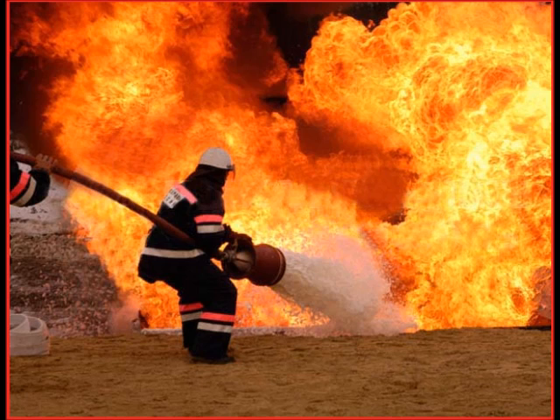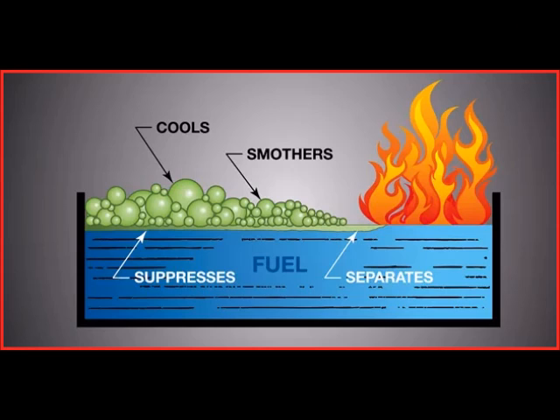Class A foams were developed in the mid-1980s for fighting wildfires. Class A foams lower the surface tension of the water, which assists in the wetting and saturation of Class A fuels with water. This aids fire suppression and can prevent re-ignition. Favorable experiences led to their acceptance for fighting other types of Class A fires, including structure fires.